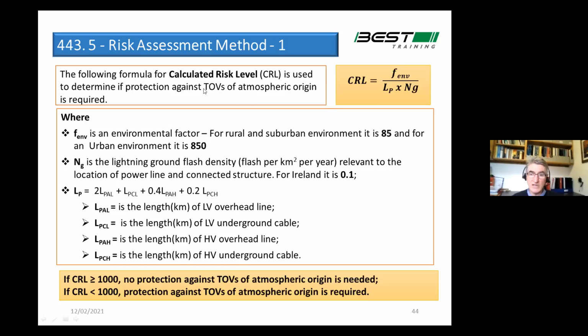It then goes on to say all other situations you must carry out a risk assessment. And it clearly says if you do not carry out the risk assessment, well, then you must put the SPDs in. So it gives you this formula here. I won't go through it. It takes a bit of detail to explain it, but it basically has 3 variables in it: an environmental factor, lightning flash density, and then another factor, this factor LP, which is basically determined from the ratio of the mix of overhead lines and underground lines, and between high voltage and low voltage. So you have to do a little bit of calculation there. The other 2 variables are very straightforward. You just pick them straight out of the wiring rules. And you carry out the calculation, and if the answer is less than 1,000, you must put in SPDs. If it's greater than 1,000, you do not need them.